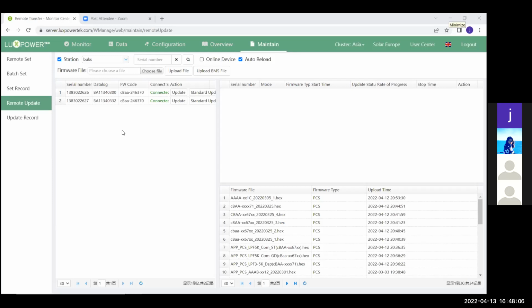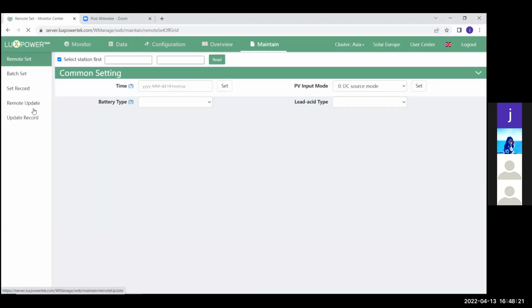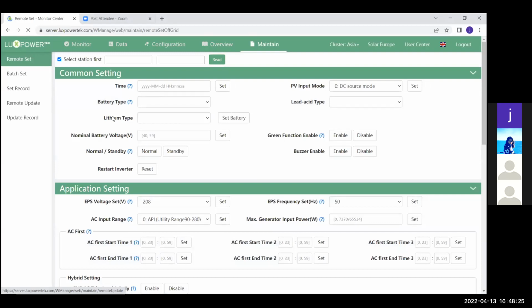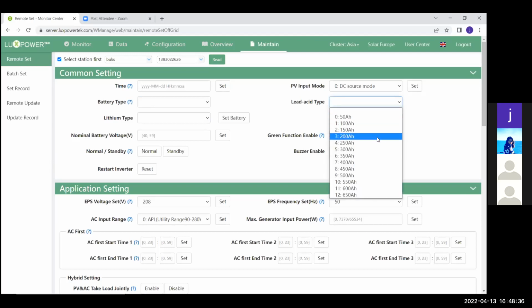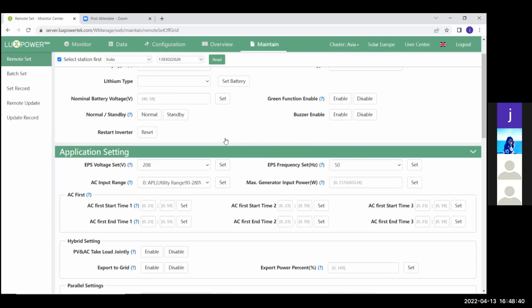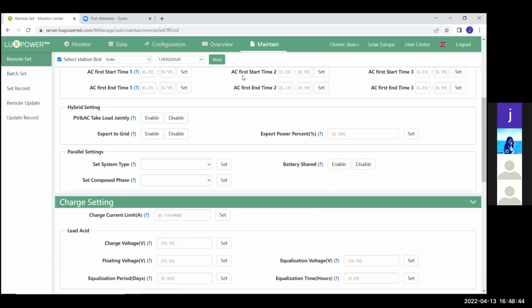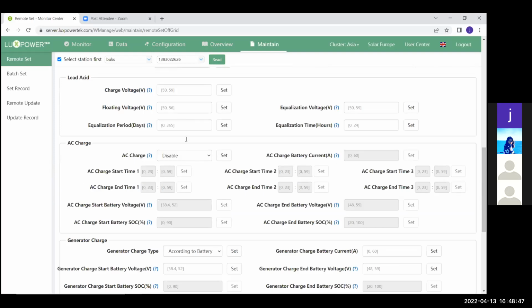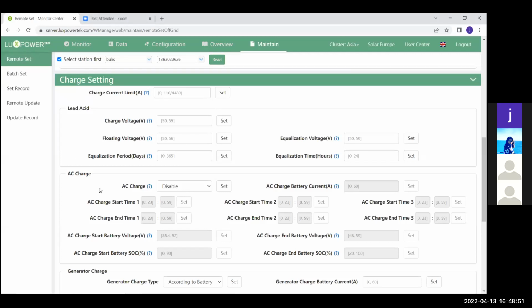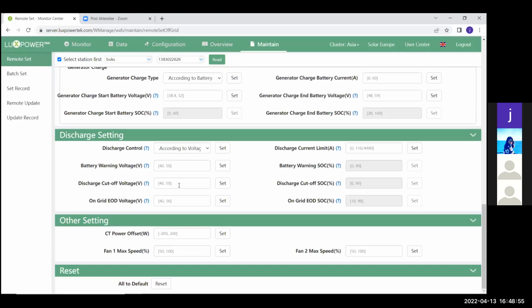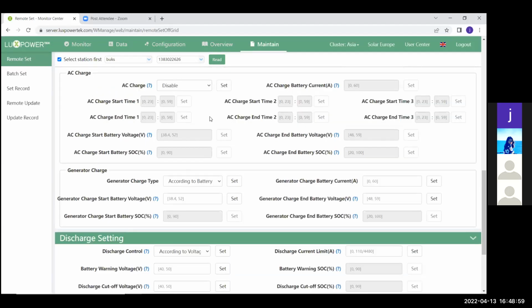At this moment, I had this question this morning on the group as well. Dustin and them confirmed that at this moment it's looking like my system is not compatible with the Narada batteries. For you to use your Narada batteries at this moment, you're going to have to come to the maintain setting. You put it on lead acid battery, and then you put in your lead acid type. You're going to put in how big this Narada battery of yours is, and then go down to your charge settings. You put in the charge voltage and float voltage that the manufacturer tells you, and all the way down to the discharge cut-off voltage, you put in the low end of your battery. So at the moment, the Narada batteries, as I understand, are not supported.